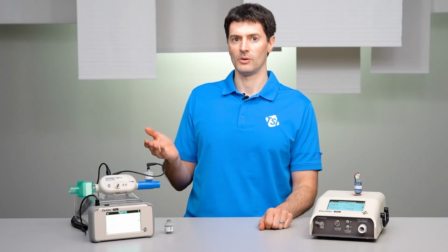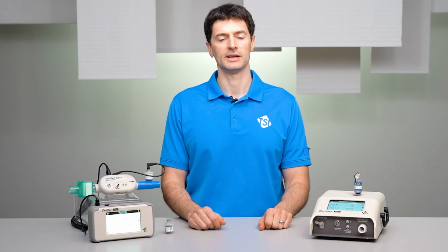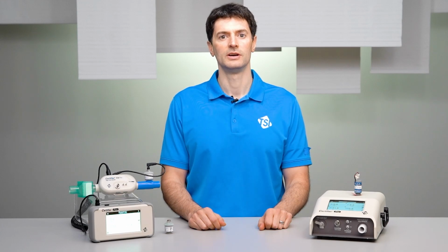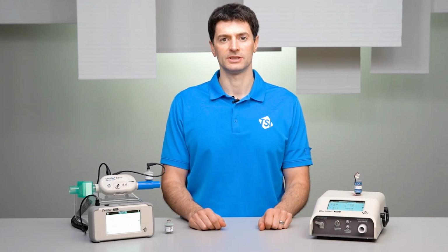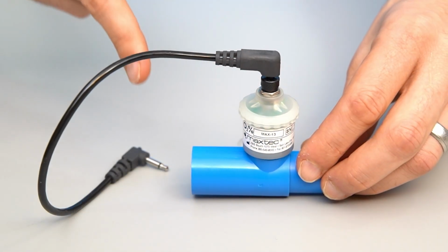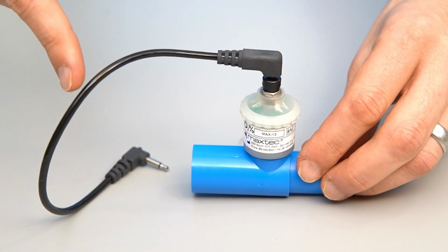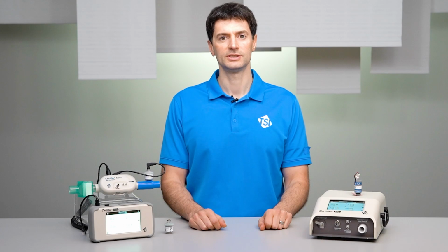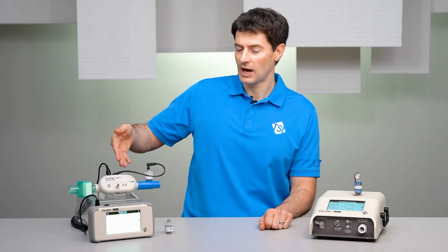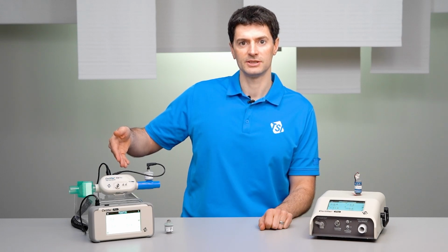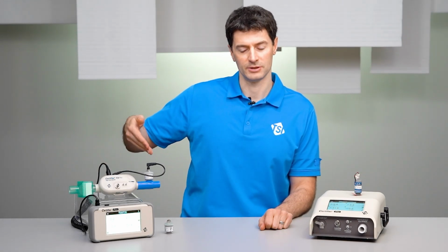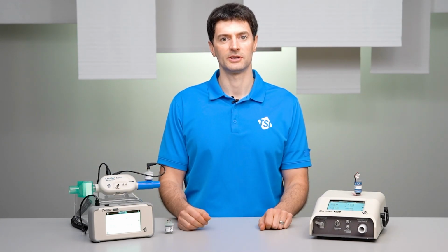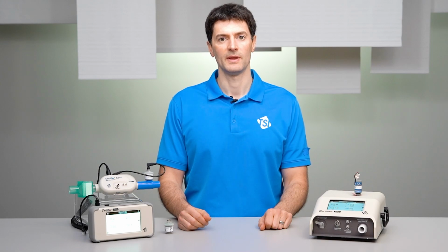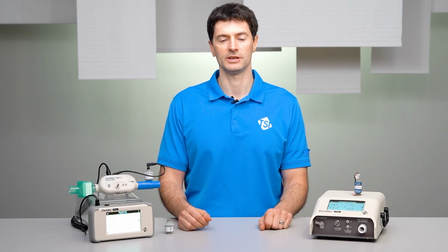For the Certifier Plus flow analyzer, the oxygen sensor is included as part of the Model 4080-F test system, or it can be purchased as a separate accessory, which is the Model 4073 oxygen sensor kit. This kit is made up of the oxygen sensor cell, airway coupling, and sensor cable. The oxygen sensor connects to the Certifier Plus high flow module and measures the oxygen concentration of gas flowing through the module.